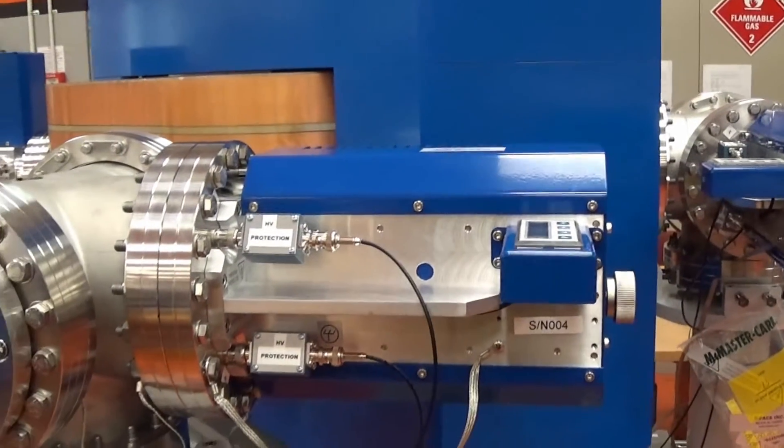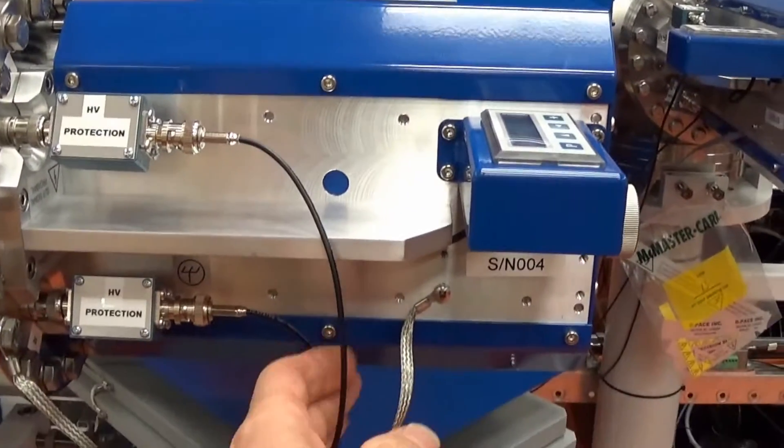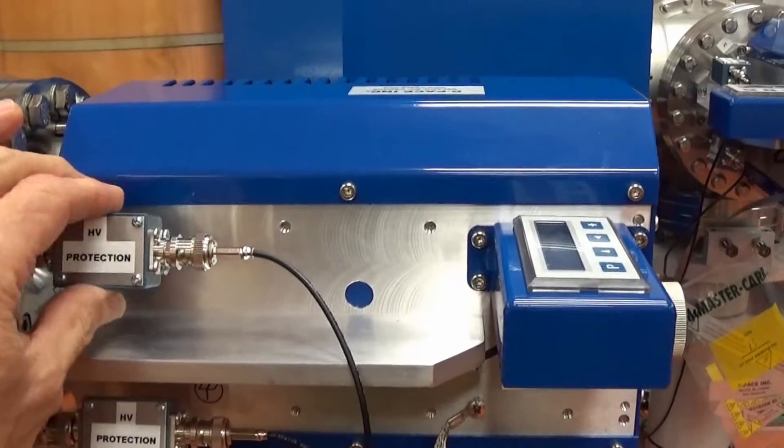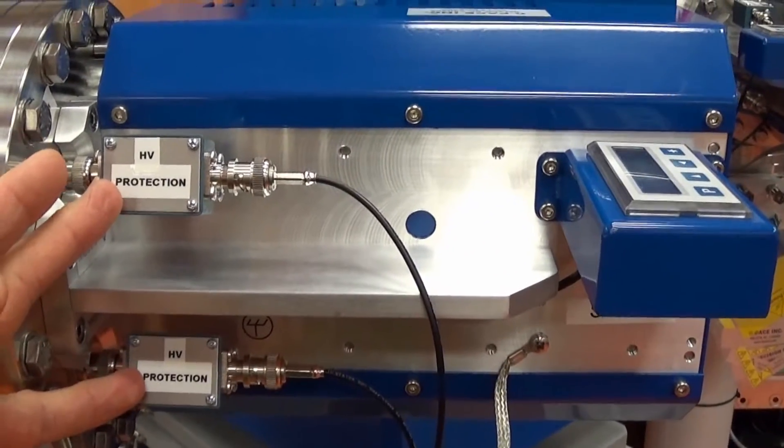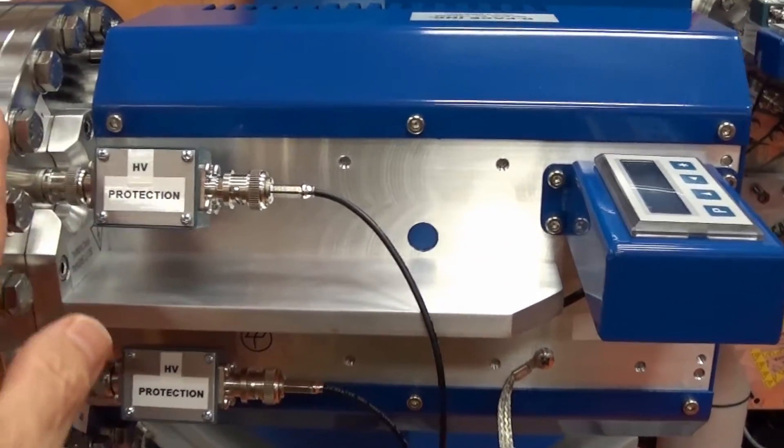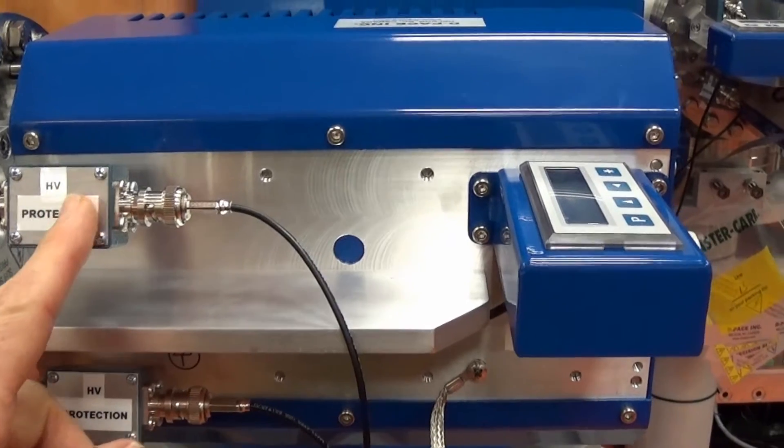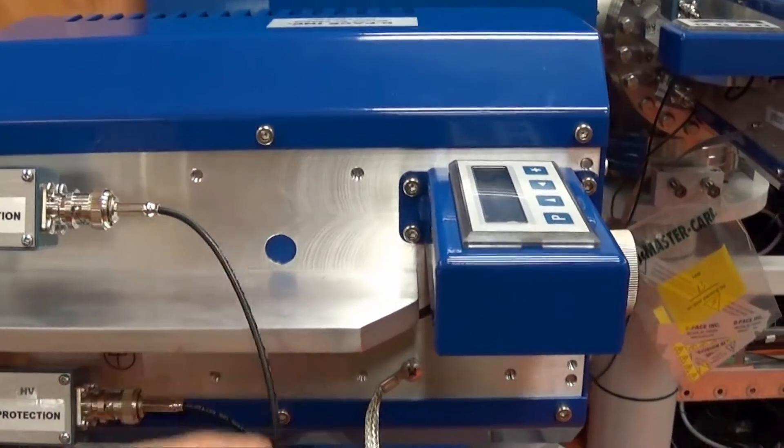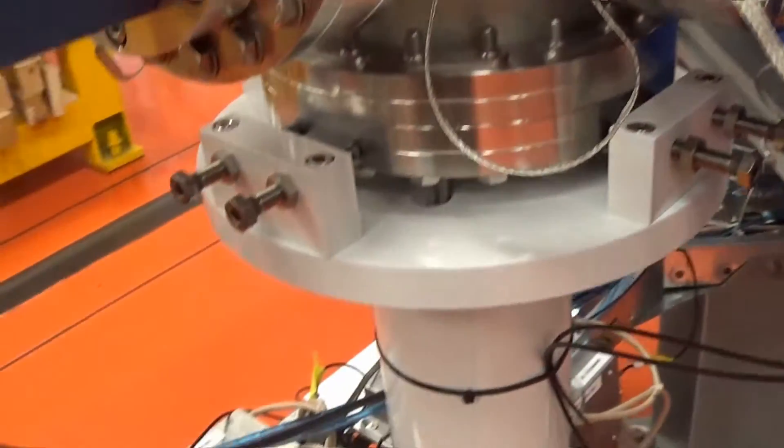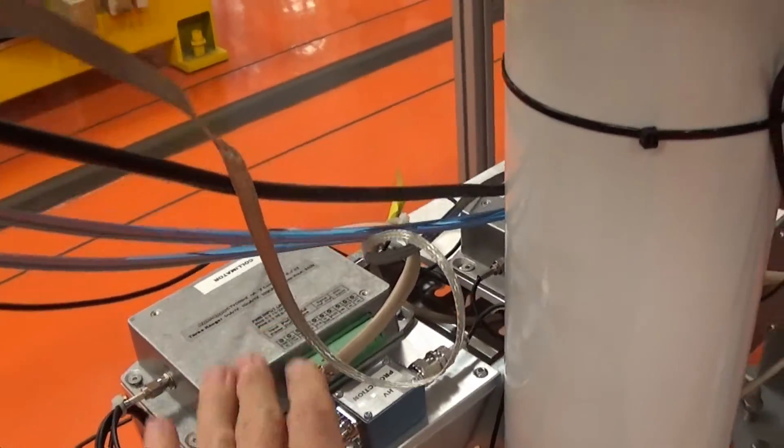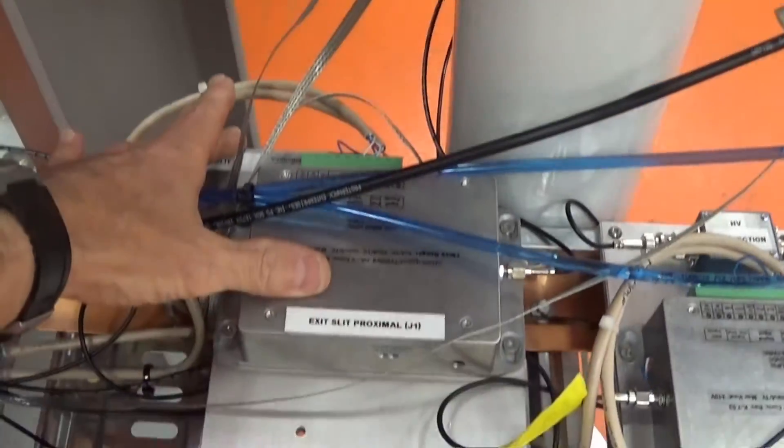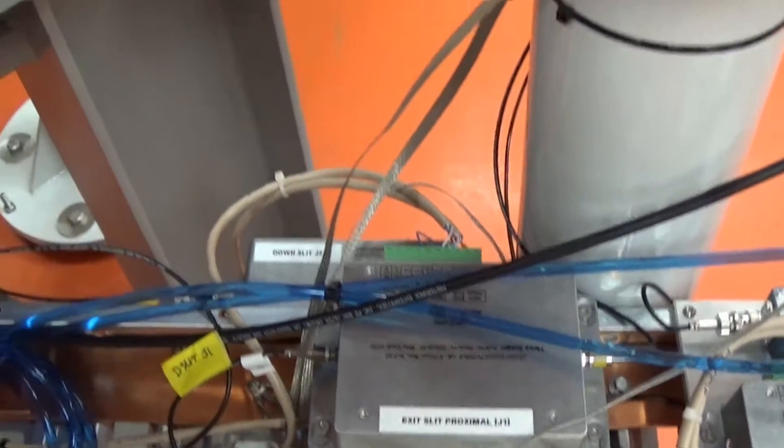We have a second set of slits here and these cables here bring the signal back from the slits. Inside these little boxes is some protection circuitry so that when the particles hit the slits they can charge up the slits to thousands of volts. You don't want that to happen so this will bleed off that voltage and just allow the current to flow down into a set of amplifiers that we have down here, and then they send the signal back to the PLCs.